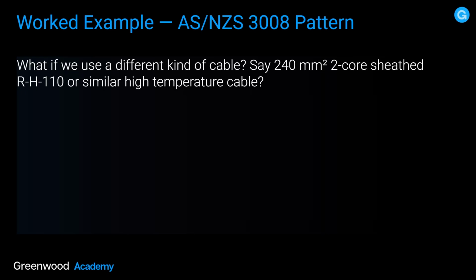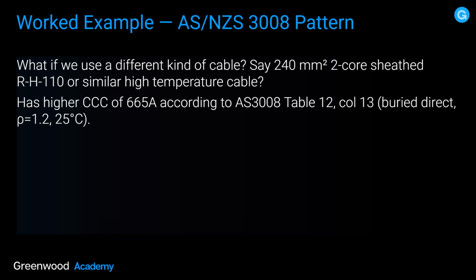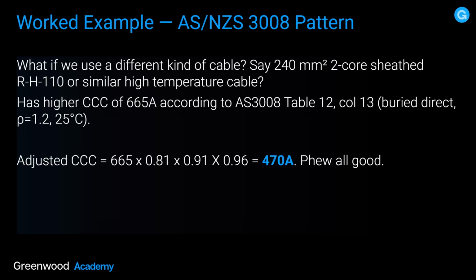We can't vary the soil temperature, and we're not really going to vary the depth of bury. So the only thing possibly we could do is bring in some engineered backfill, and we'll look at that later on. What if we use a different kind of cable? Say 240 mil, 2-core sheath, RH110, or a similar high temperature cable. It has a higher current carrying capacity of 665 amps according to AS 3008, Table 12, Column 13, buried direct, assuming a thermal resistivity of 1.2 with a soil temperature of 25 degrees C. So the adjusted current carrying capacity is 665 times 0.81 times 0.91 times 0.96, and that's 470 amps. Phew, all good.